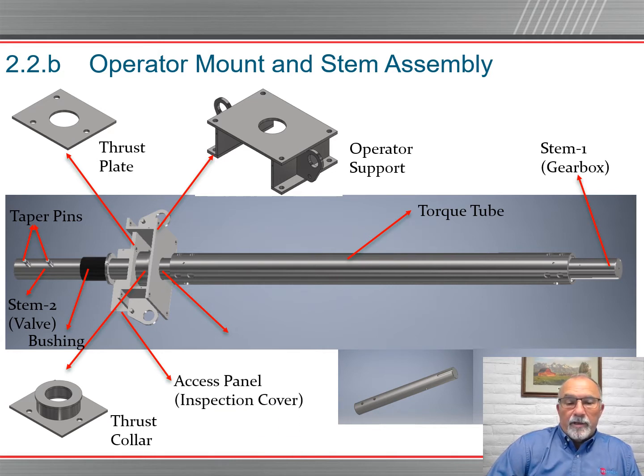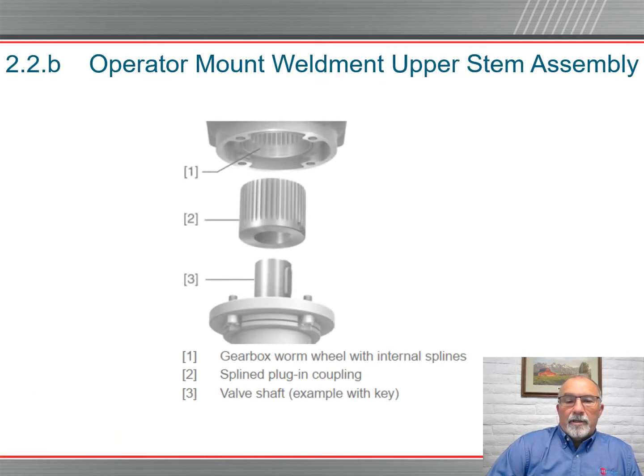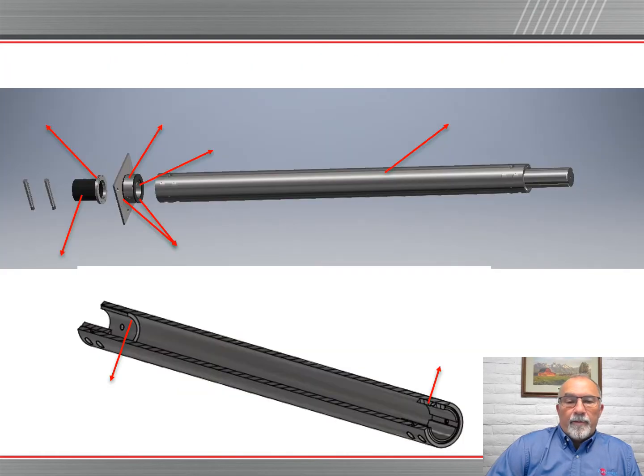The access panel is an inspection cover. We've removed it there so you can see clearly what's going on. The torque tube itself, stem number 2 and stem number 1 are shown in their design. The operator mount weldment, the upper stem assembly, zoomed in. So you have the gearbox, the worm wheel, the internal splines, the spline plug-in coupling, and then of course the valve shaft. And in this example we have a key.